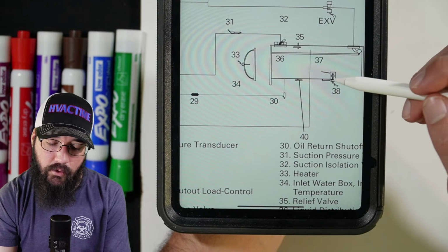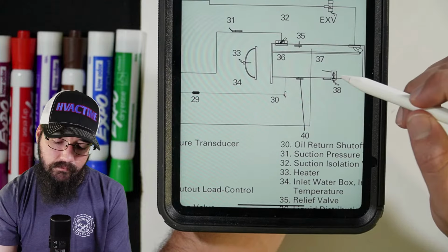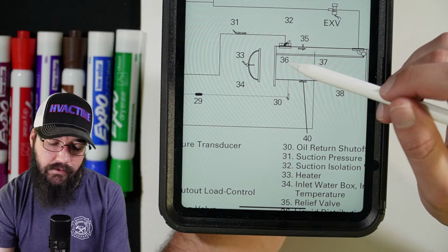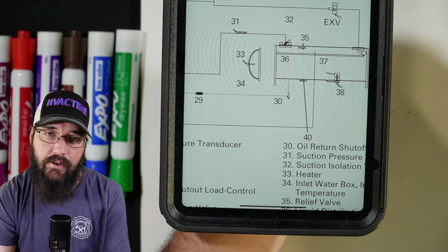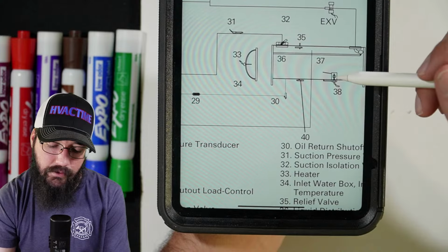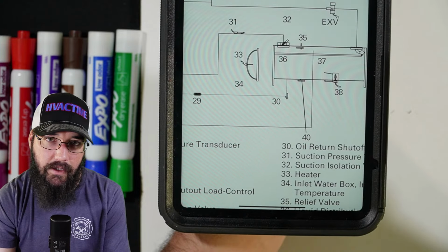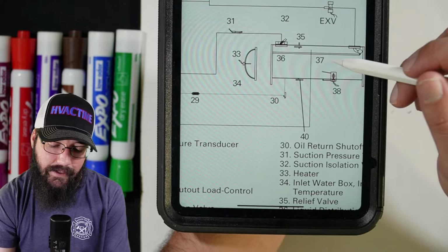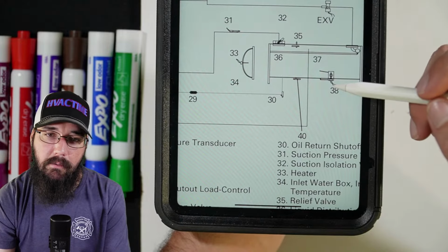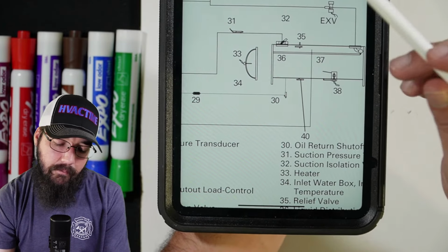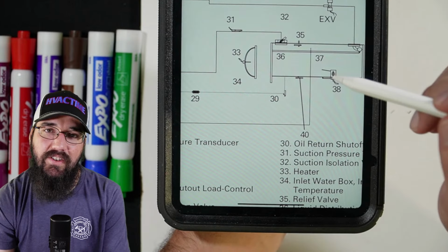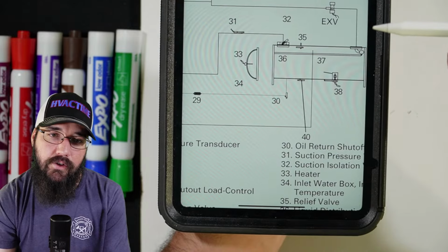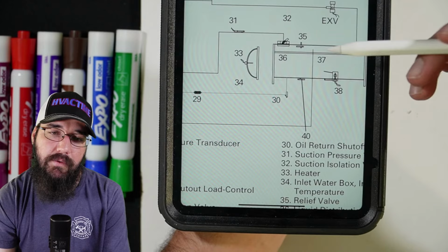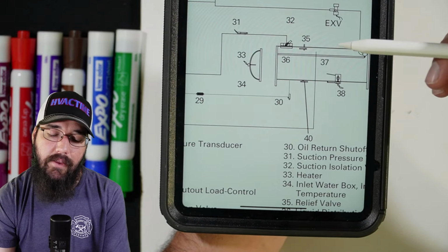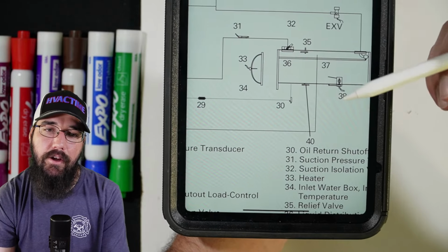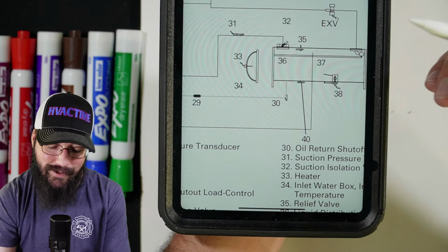Basically what that'll look like is you'll see a normal or a high liquid level position, but yet you're running suction limiting, and you've got really high suction superheat coming back into the compressor. When you see those conditions, but yet your level sensor says it's normal, or it's high and it needs to feed less, that's an obvious sign, okay, probably oil in this case. Part of the goal is to get the machine to just stay online long enough to get that oil out. Because eventually, if we can let it run at a minimum state, get that oil back out of the evaporator, that will start to correct itself. But we have to have operation and runtime in order to make that possible in the first place.